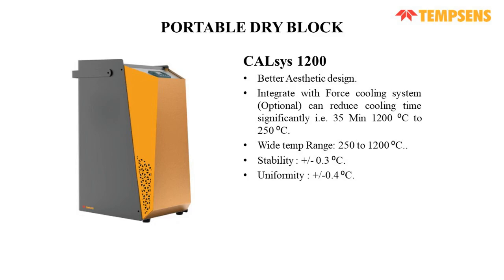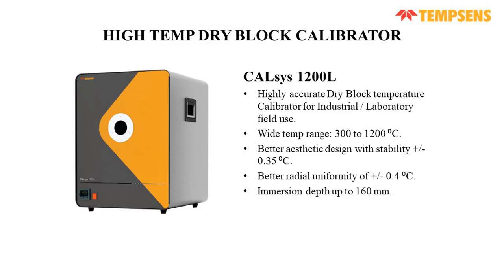Next, we have CALsys 1200, the portable one, with a wide temperature range of 250 to 1200 degrees centigrade, with a stability of plus minus 0.3 degree and uniformity of plus minus 0.4 degree. It can cool from 1200 to 250 in just 35 minutes. Celsius 1200L is a very highly accurate dry block temperature calibrator with a temperature range of 300 to 1200 degrees centigrade. It has stability of plus minus 0.35 degree and a radial uniformity of plus minus 0.5. The immersion depth is up to 160 mm for this model.